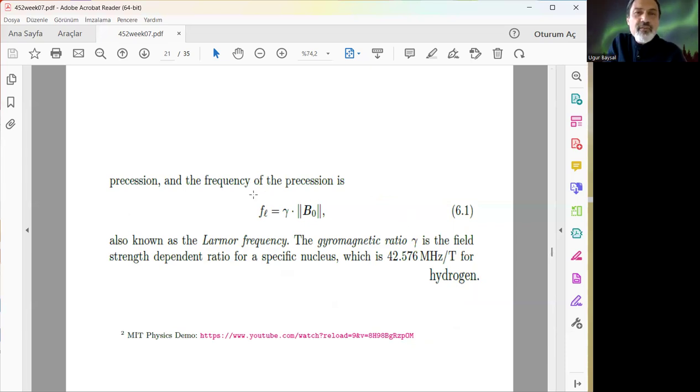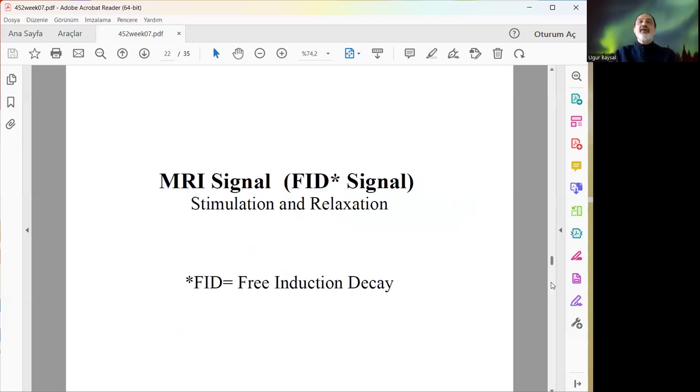And this is the formula for the frequency of excitation. This is called the Larmor frequency. For MRI, that's required. You have to apply exactly this frequency to excite the nuclei in the body, and the antennas of the systems are tuned at that frequency for transmit and receive of electromagnetic excitation. So after you send this energy, the tissues reflect back their own magnetic resonance signals.